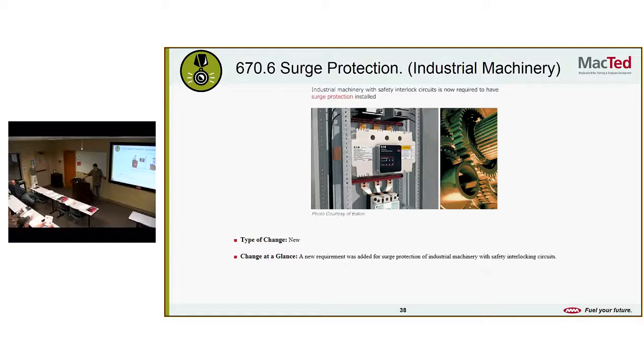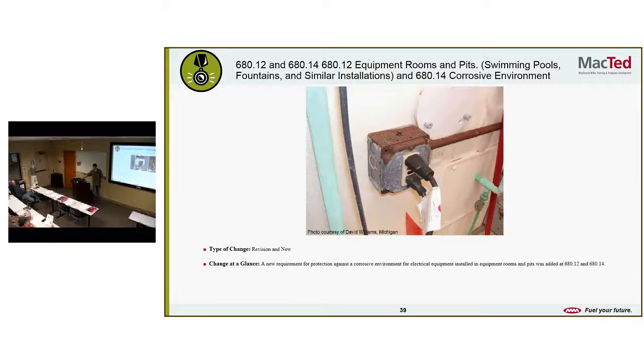Surge protection for industrial machinery. A new requirement was added for surge protection of industrial machinery with safety interlocking circuits. So if you have safety interlocking circuits on industrial machinery, now you need surge protection. That sounds like a good idea, so it doesn't blow out your interlocks and then provide unsafe working conditions for industrial machinery. I like it.